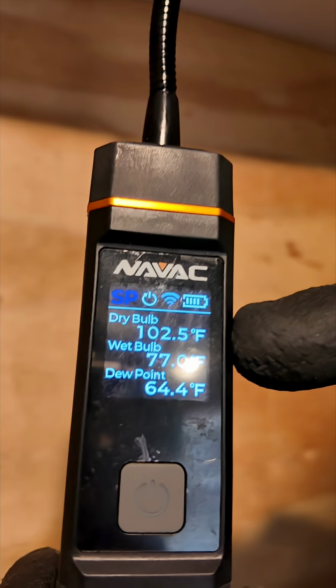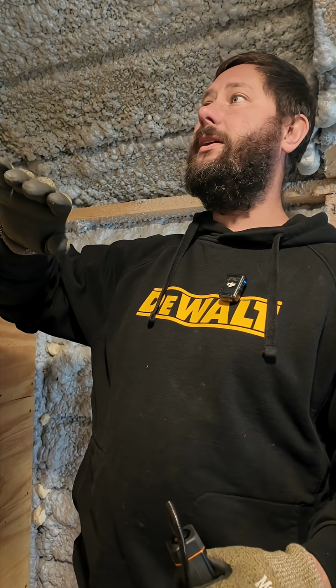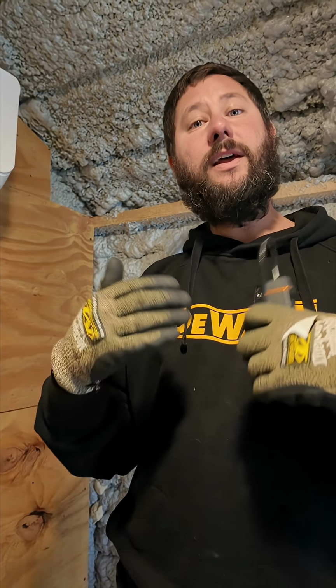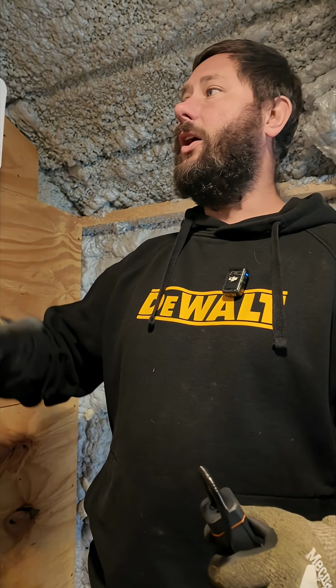You see that top number? It says 102, right? So right now we got a 40-degree temperature split between our return and supply. During the cooling mode, you should have a temperature split of at least 20 for a mini split. So that means if you're pulling in 70 degrees, you need to be pumping out 50 during cooling. During heating, you have even a higher temperature split. So we should have at least 30 degrees.